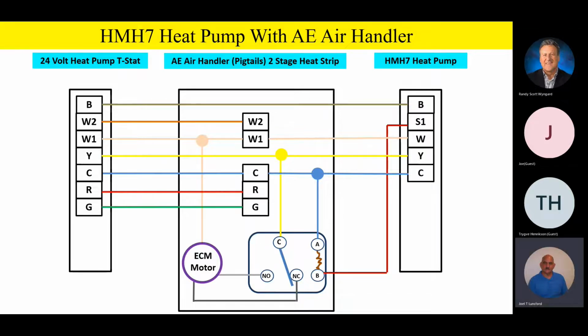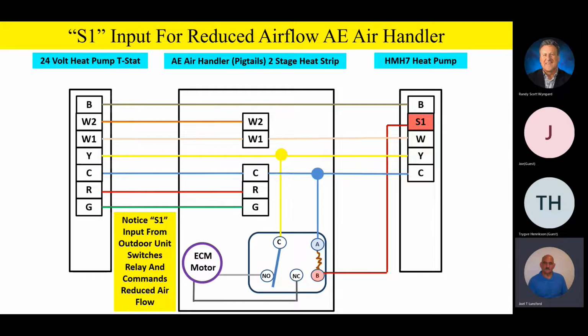Now watch this. Let me go ahead and do an animation real quick. Watch the screen closely, everyone. When I get an S1 output from the outdoor unit, we energize S1. What it does, it energizes the relay. It switches from a normally closed to normally open set of contacts. And you'll notice that S1 input from the outdoor unit actually switches the relay and commands reduced airflow.